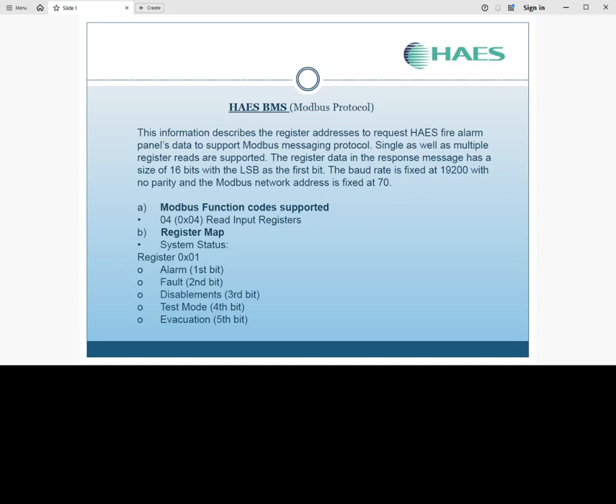B. The register map. System status. The register is 0x01. The alarm is the first bit. Fault will be the second bit. Disablement's third bit. Test mode fourth bit. And evacuation the fifth bit.